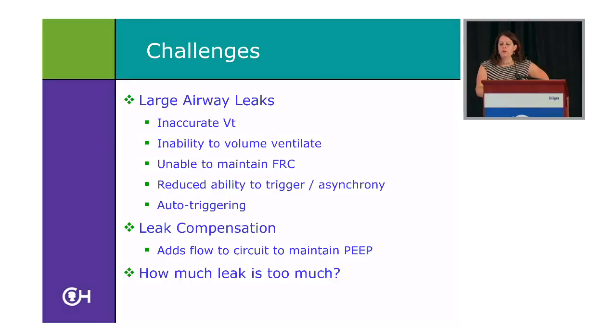So really, a lot of the new ventilators have come up with leak compensation. This has been out for years, which is great. It helps to compensate for some of the leak a little bit, and what they do is add additional flow to the circuit so that they can maintain the PEEP level that we have set. There is a group of neonatologists that don't really like the leak compensation, because that extra flow that they're adding, the infant can pull from, and they can get extra tidal volumes and extra support with their breaths that they can't control for. So, you know, again, you have to weigh your pluses and minuses.